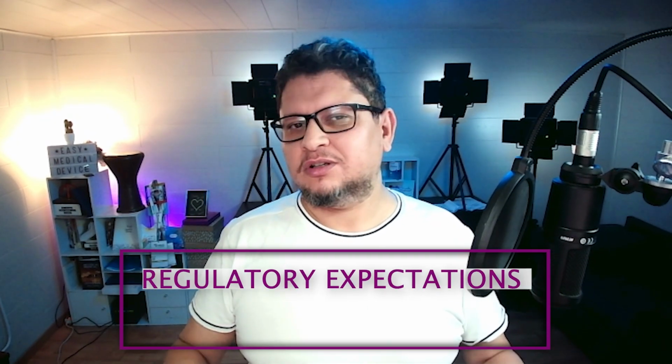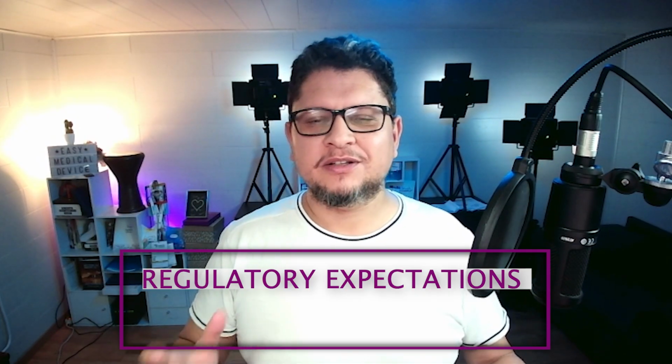So what do regulators now expect for post-marketing surveillance for software and AI? If you look at EU MDR and IVDR, they want your post-marketing surveillance to cover all the real-world data and real-world performance, and also to be included inside your PSUR. For software, this means you have to collect evidence that your updates didn't degrade your safety, performance, etc. And for AI, it may also include performance across subgroups, because we talked about biases also.